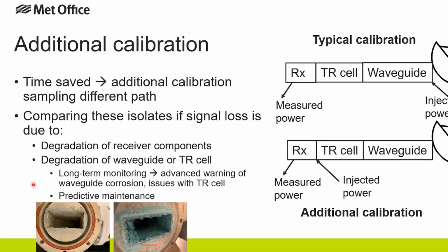So we're hoping that this will give us the opportunity to do long-term monitoring and get advanced warning of any waveguide corrosion or issues of the TR cell. So the plan is that we can then do predictive maintenance to take action before we reach the point of failure.